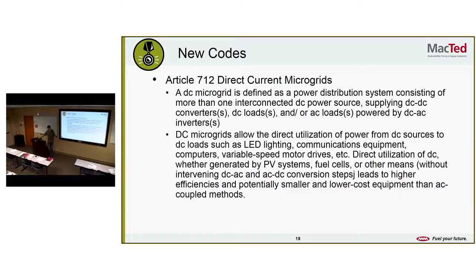It's Article 712, direct current microgrids. So microgrid is the same thing as the last one, power distribution consisting of more than one interconnected DC power source, supplying DC to DC converters, DC loads, DC to AC. They allow direct utilization of power from DC sources to DC loads such as LEDs, communications equipment, computers. So probably like UPSs is what that sounds like. So they've added an article for that because we're seeing a lot more DC out there. Think about your DC motors that you're seeing in air handling systems versus your standard PSC motors. Everything's kind of DC now.